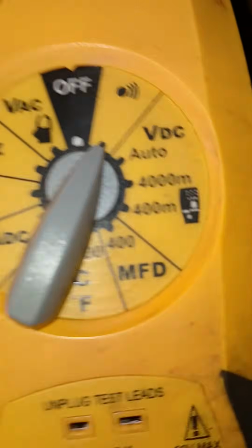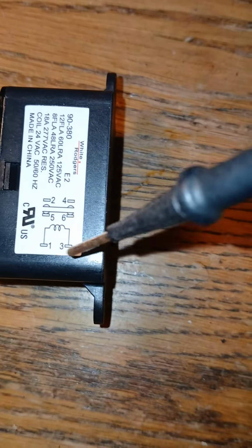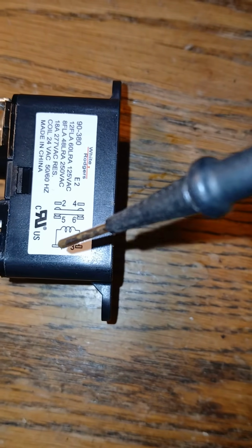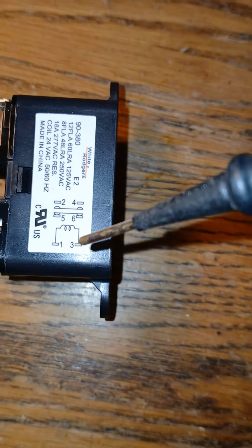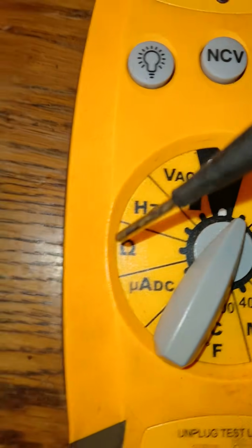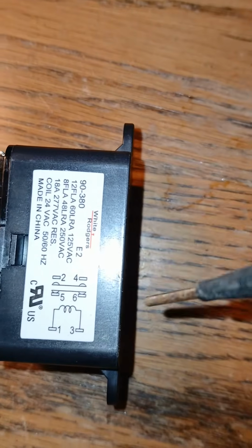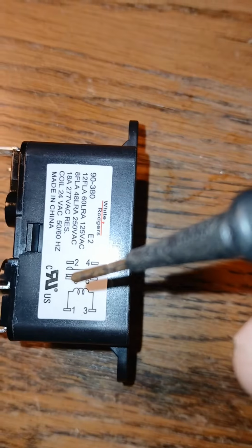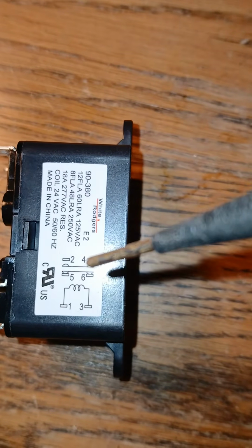Now we go between 2 and 4, and we get nothing, which is good because 2 and 4 should be open. If we turn this over and look here, we've got the coil here in this fashion. We tested this with ohms. We got between 70 and 80 ohms with this coil here. The low voltage side, the 24 volts perhaps, but we tested this in ohms, remember. Then the top part, we flip to continuity, and so we tested this. As we can see, the relay is closed between 5 and 6, and 2 and 4 is open.